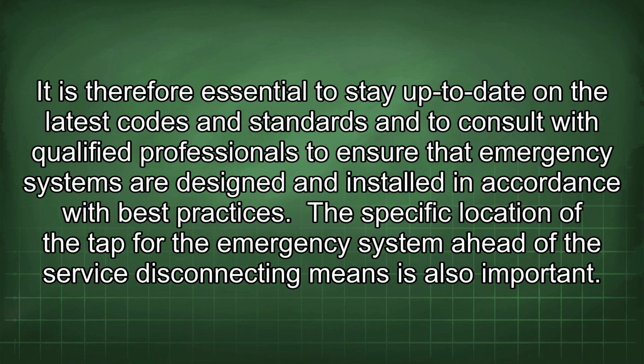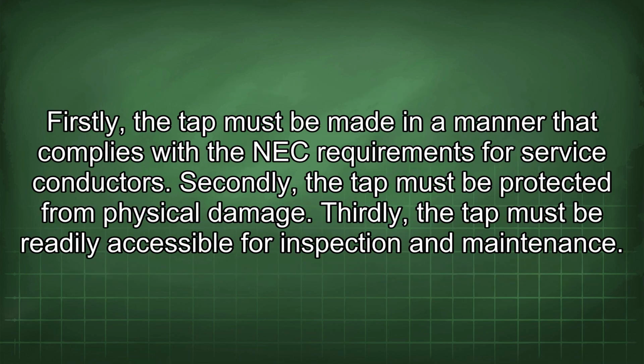The specific location of the tap for the emergency system ahead of the service disconnecting means is also important. Firstly, the tap must be made in a manner that complies with the NEC requirements for service conductors. Secondly, the tap must be protected from physical damage. Thirdly, the tap must be readily accessible for inspection and maintenance.